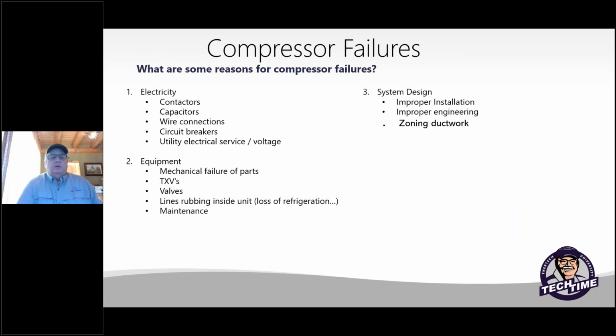Today I want to talk a little bit about some compressor failures and some of the reasons why they fail. Electricity is probably the biggest proponent of problems. Contactors, as we all know, welded contact points cause a compressor to run without being able to shut down on safeties. Capacitors, obviously if they're bad, we know that the amp draw of a compressor goes way up, and so they're running out of its normal amp ratings and creates hardships on the compressors as well.